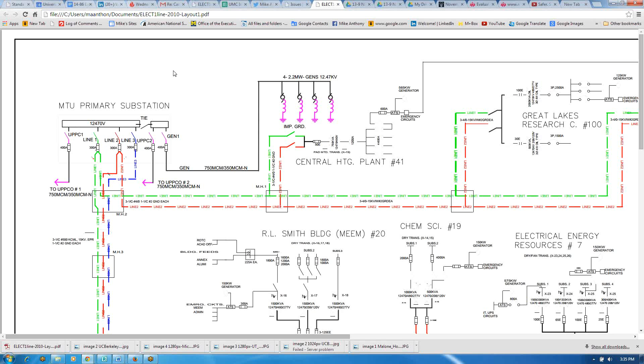I don't know if you have any instrumentation on your switchgear here. You probably do. But with fuses, in our case, we have a lot of circuit breakers, and a couple things we have to consider is that in some regimes the phase-to-phase ground in an impedance ground system isn't picked up right away. It's one of the more statistically less likely faults. Most faults are solid ground. We feel, and it seems to be the judgment of large parts of the process control industry, that impedance grounding is worth the trade-offs.